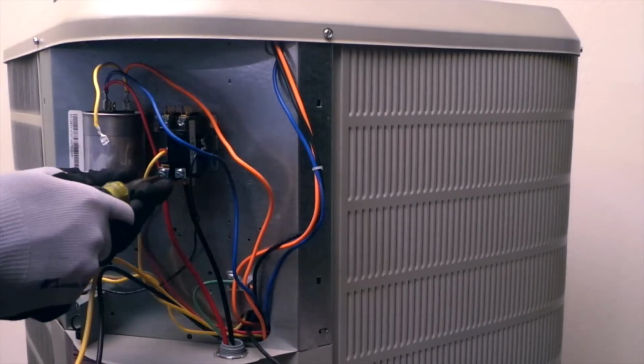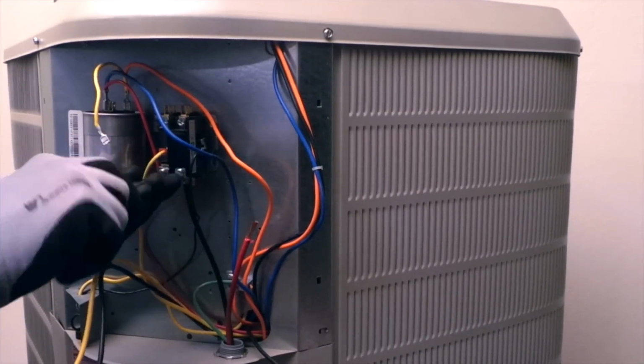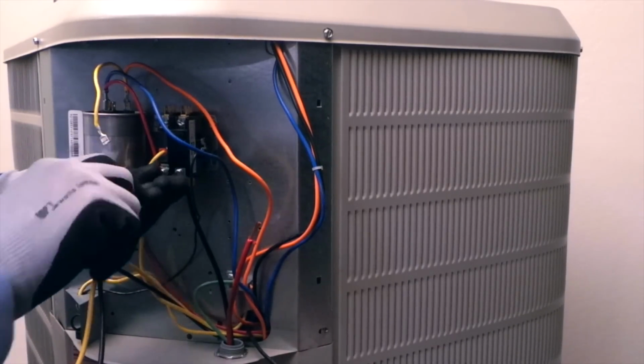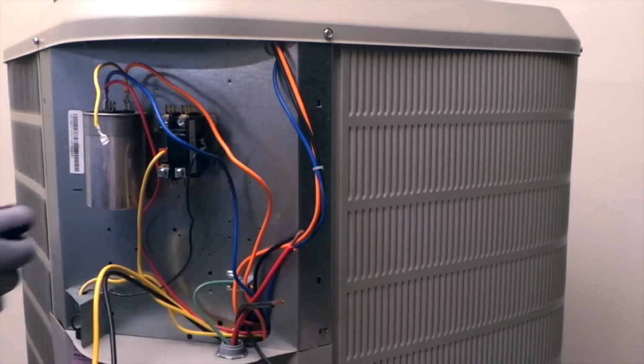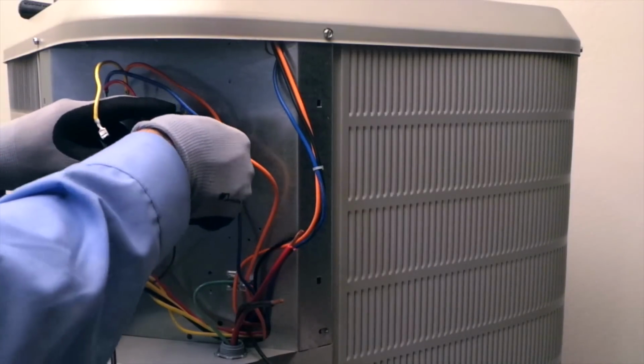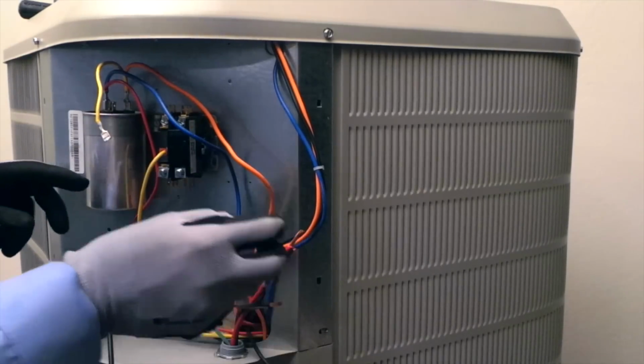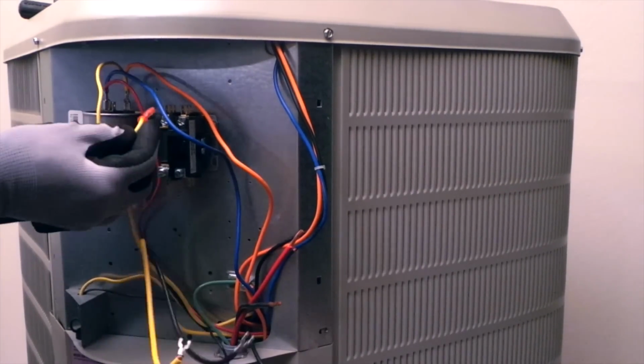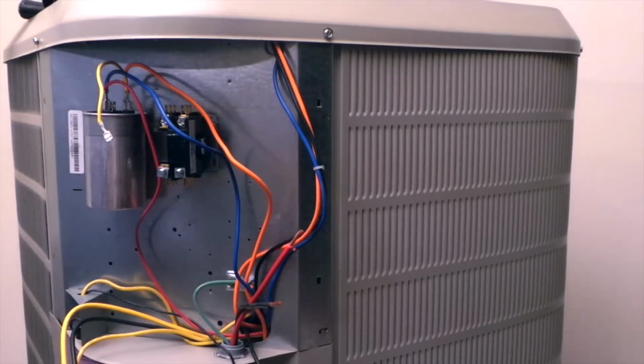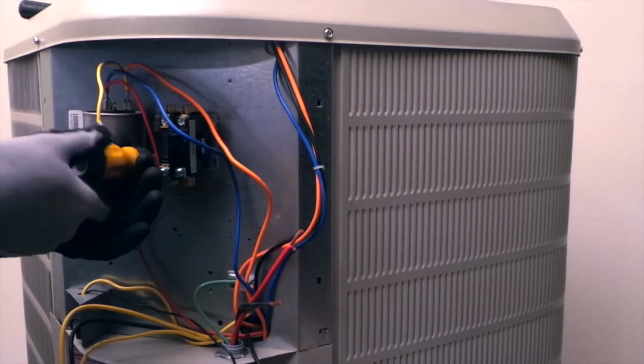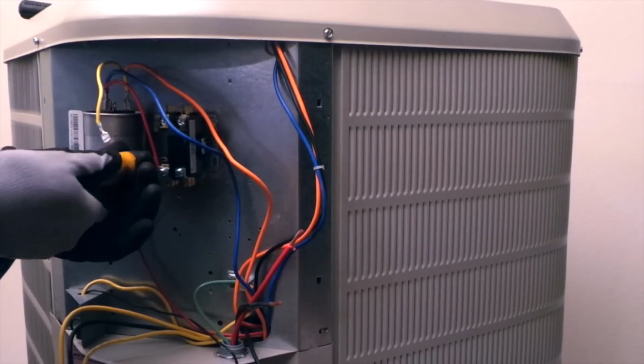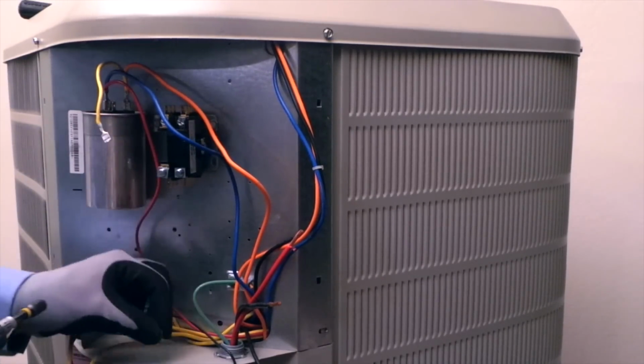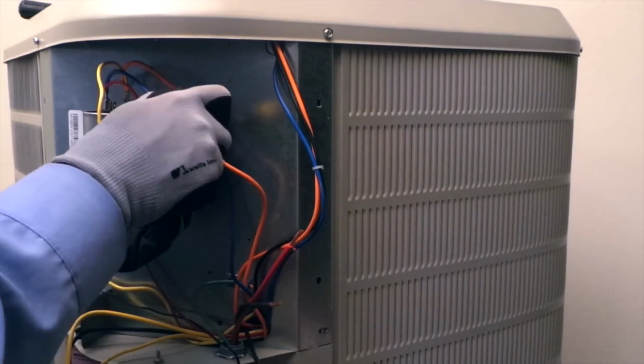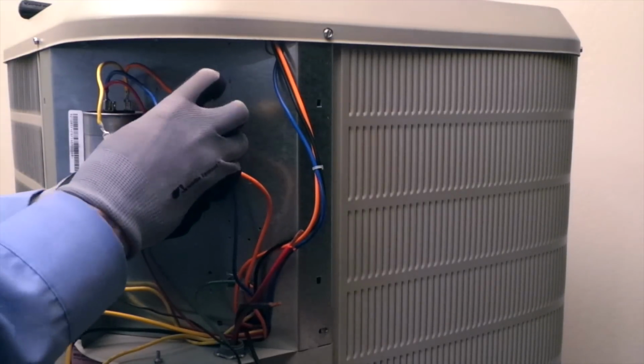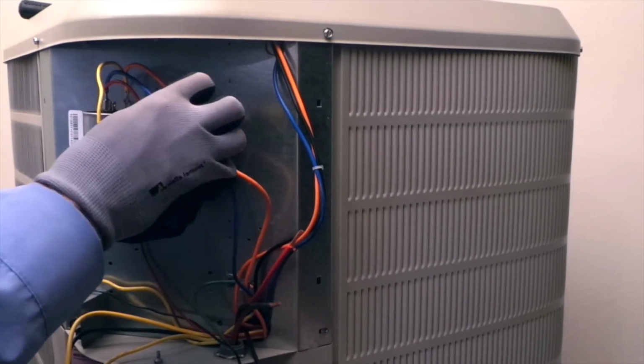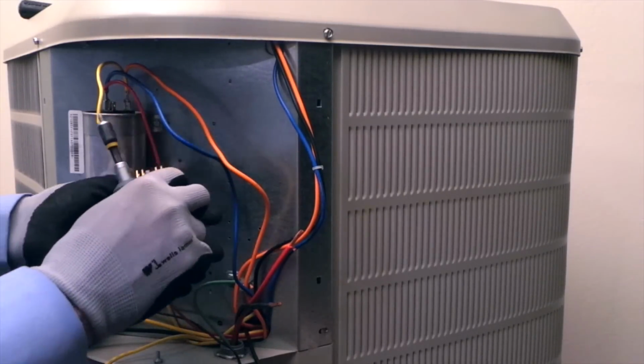Now we will loosen the screws on the lugs on the bottom of the contactor and remove the supply voltage wires coming from our disconnect panel. At this point, we can disconnect our low voltage wires from the coil on the sides of the contactor. With all the wires removed, we're now ready to remove our contactor. We take out both screws on the back plate of the contactor, removing it from the condenser. Before we do that, we want to make sure of the position. We have a single pole contactor that has contacts on one side of the contactor and a shunted circuit by a bus bar on the other.